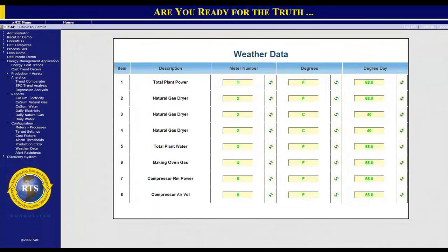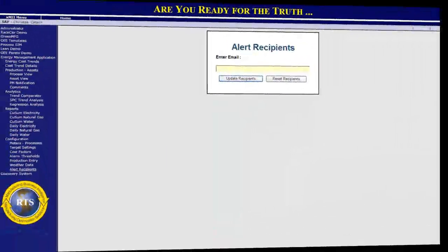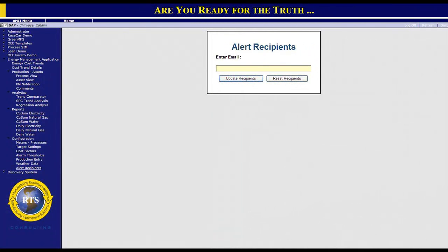Configuration screens are also available for entering degree days for total energy consumption target adjustment. In many cases, outside temperature may have an impact on process energy consumption. This can be manually inputted, or preferably through temperature sensors around the building, or obtained via the internet from a standard website providing degree day information. Email setup for alerts and recipients is also all within the composite application.